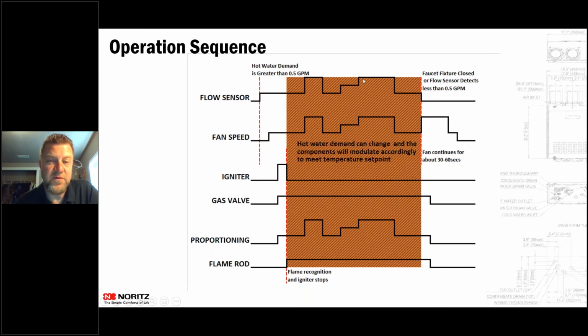It's going to sense that flow. So if it's changing all the time, people turning things on and off, that flow rate is going to modulate up and down, up and down, which is also going to change that fan speed, which is also going to change the proportioning down here with the BTUs. The more water that's going through that unit, the higher the BTUs are going to be to heat that water, and the less it's going to bring that down.